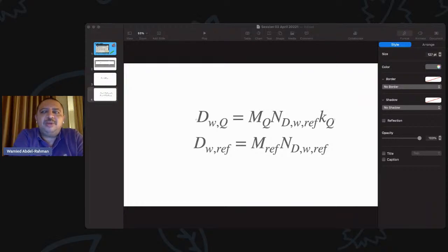to establish electron equilibrium. The problem in this measurement is that the cap is now a source of scattering, and the larger the cap, the more scattering it will produce to the chamber. That's why this definition of peak scatter factor is usually not used for measurements at high energies at all.